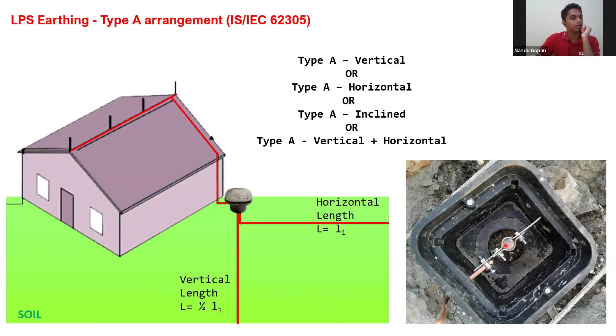Now, what is type B earthing? If you ask me, suppose you have this building, for example, and this is the top view of the building. This is how you see it from the top view. So if there is a ring which is going around the building, and suppose that is this ring, and this ring is interconnected to the down conductors, it is called a type B arrangement.